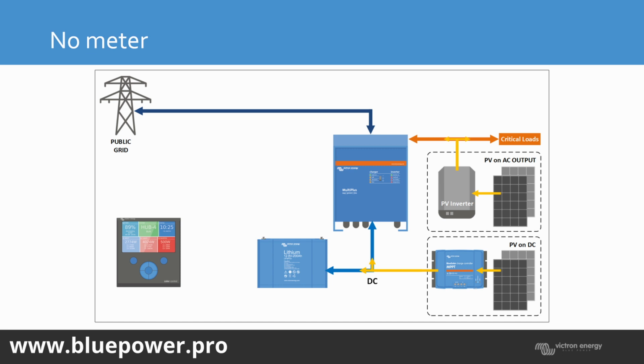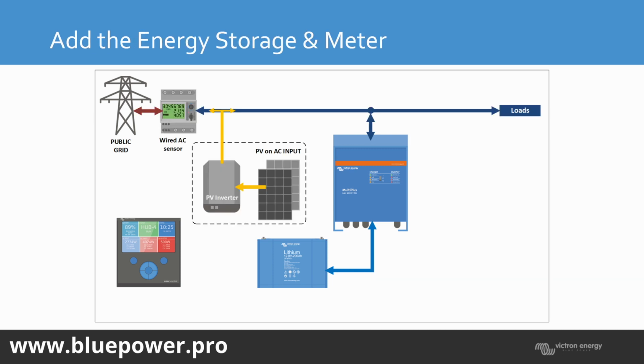So just quickly, the other PV you had by the grid, is that non-critical loads? Yes. So then it's non-critical PV, then critical, and then DC. Yes, so the blue line is non-critical, so it's going to be everything connected directly on Eskom. So if you've maybe got a 5 kVA inverter and you want to supply your geyser with solar, but you don't want to supply it when there's a power failure, then you can connect your geyser onto the Eskom directly still after the meter and have excess PV power from the DC bus or from the PV inverter feed your geyser.